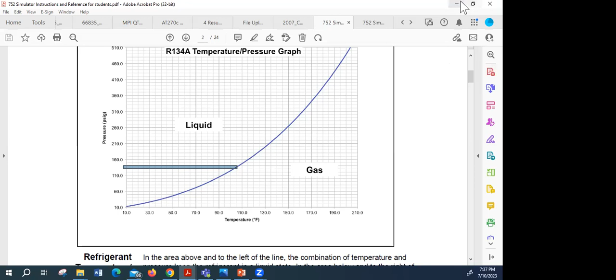And the temperature was 105 degrees. So the first thing we could do right off the bat, we could look at this. What pressure should that be at 105? This would be about like 110, 120, 130, maybe 135, 140, right around there. Yeah, that could be right. I can't tell, but maybe we're in the ballpark, around 130 there. That's a little rough, huh?